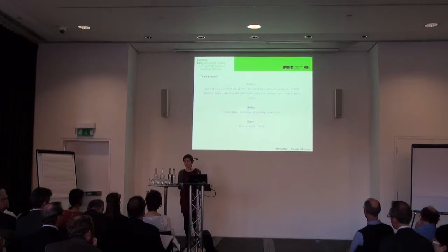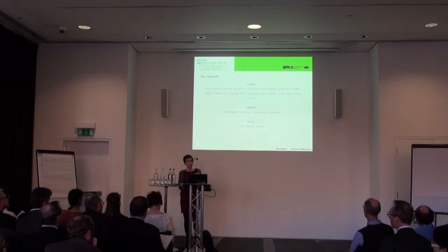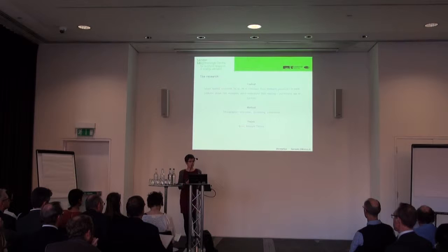The commissioning process involves the completion of a commissioning checklist. This is a grey A4 form that's included at the end of the manufacturer's instruction book. This sheet includes the completion of technical information, for example, carbon monoxide emissions, gas flow rates to the boiler, but also there are elements that involve the customer.